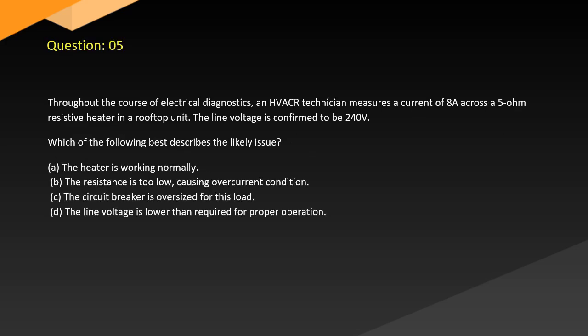Question 5. Throughout the course of electrical diagnostics, an HVACR technician measures a current of 8 amps across a 5 ohm resistive heater in a rooftop unit. The line voltage is confirmed to be 240. Which of the following best describes the likely issue? A. The heater is working normally. B. The resistance is too low, causing an overcurrent condition. C. The circuit breaker is oversized for this load. D. The line voltage is lower than required for proper operation.